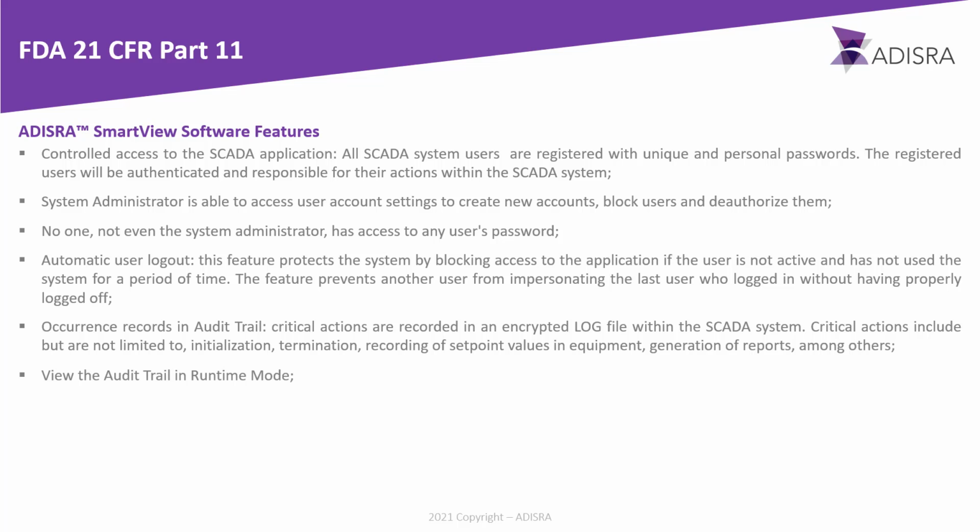The SCADA system must have tools that allow the information contained in the files generated by the system to be viewed in a readable format. The visualization can be performed by table, graph, report, or other viewable form. All electronic data records, whether from remote units, sensors, or configuration files from the SCADA system, must be stored in an encrypted format so that they cannot be opened in other systems.